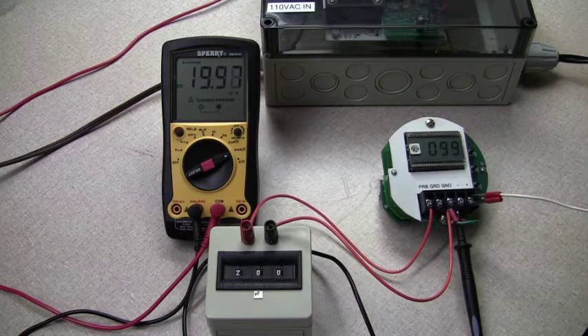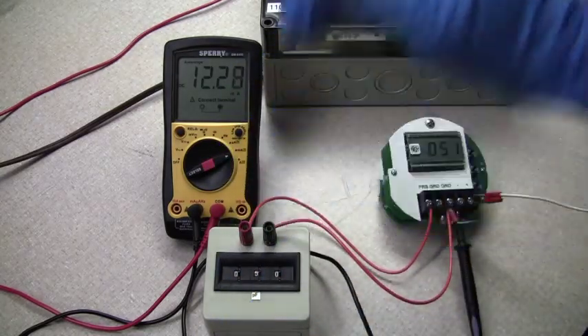You are finished setting your high set point. Now you're ready for normal operation. And that completes how you calibrate the 4 to 20 milliamp and how you calibrate your low and your high set points.